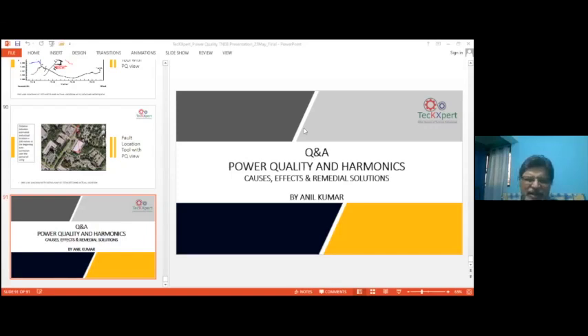You have a certain way of telling, for example, whether the harmonic power flow is on the positive side or the negative side, as I mentioned before, the 4-quadrant operation. In a solar plant, if you're generating and exporting power, the power flows in one direction. When you're importing, the power flows in the other direction, because the phase angles are different. Similarly, harmonics generated in one direction or the other can be found out, but it cannot be an accurate method.